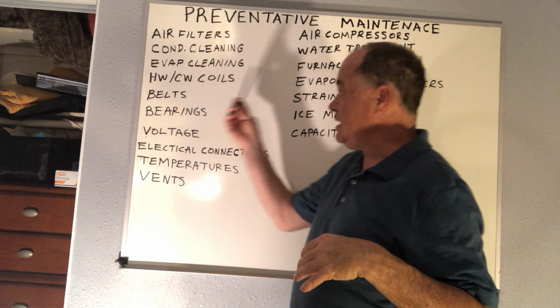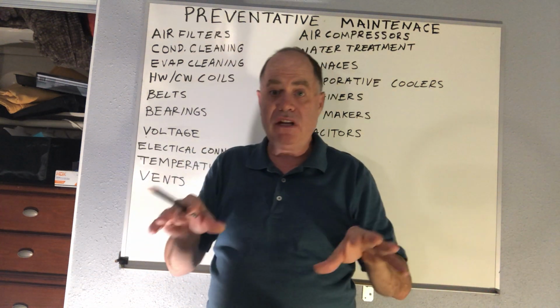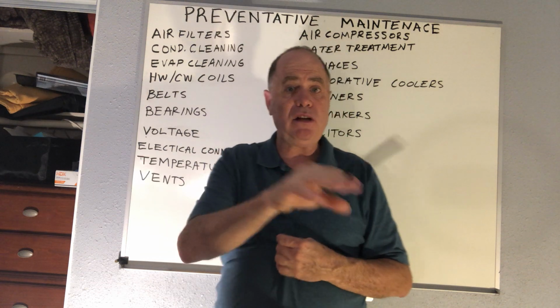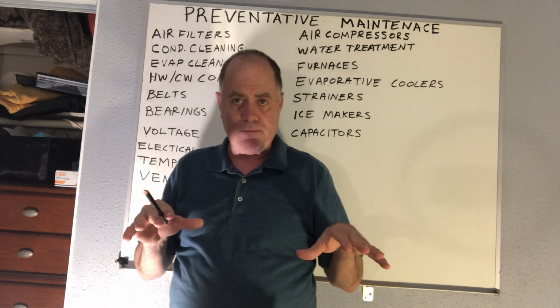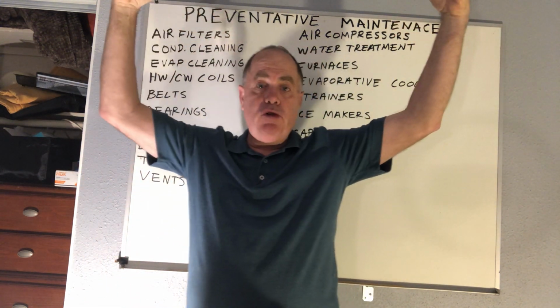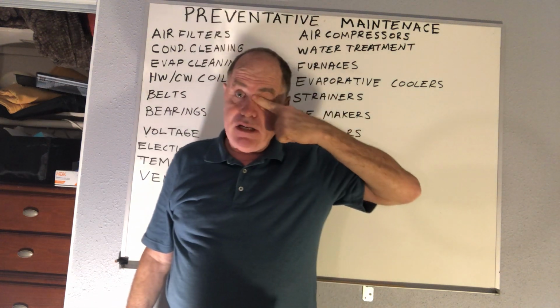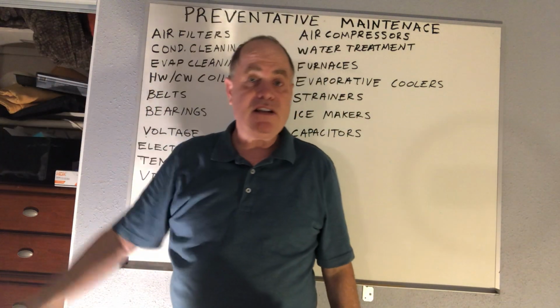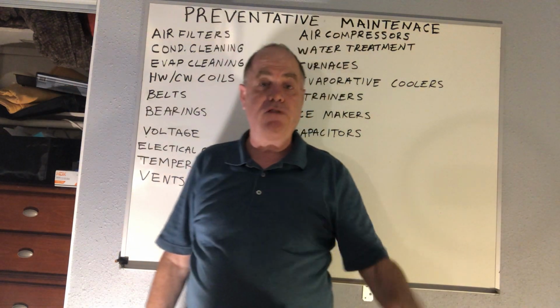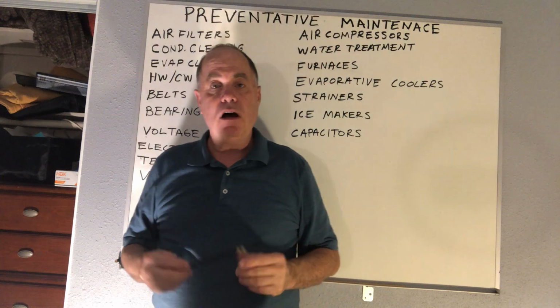And I want to say this about preventative maintenance, is that every building and all the equipment and how it's running and where it's running is unique to that building. So you may have a slightly different preventative maintenance program for each machine or each building based on the conditions there, okay? If you have a building and you have package units way up on the roof and it's a very clean area, maybe you don't need to replace air filters that often. However, if across the street they start a massive construction project with a lot of dust, guess what? You've got to change your air filters more often, clean your condensers more often. So you kind of have to see what the circumstances are for that equipment when you create a maintenance program.